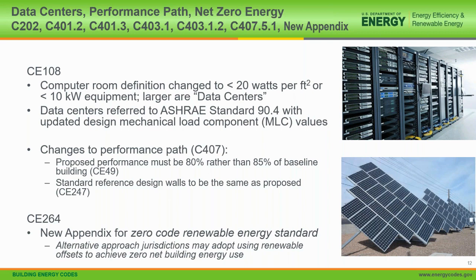There's also another minor change: standard reference wall designs will now be the same in the proposed as the baseline. So whether it's a wood frame wall, a steel frame wall, or a masonry wall, those are going to be the same in both models. All right, CE 264 is a complete new appendix. It allows for a zero code, net zero building code that essentially uses renewable energy, whether it's on-site photovoltaics or off-site purchased photovoltaics, to make up the difference so that a building could be accredited as net zero. And that may or may not get adopted by certain jurisdictions. It's a separate appendix in the standard.